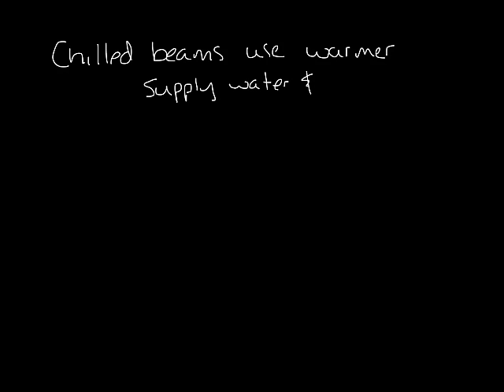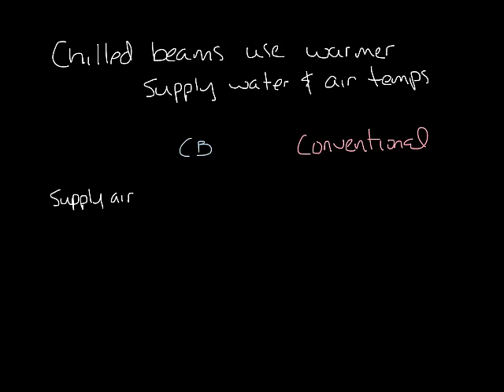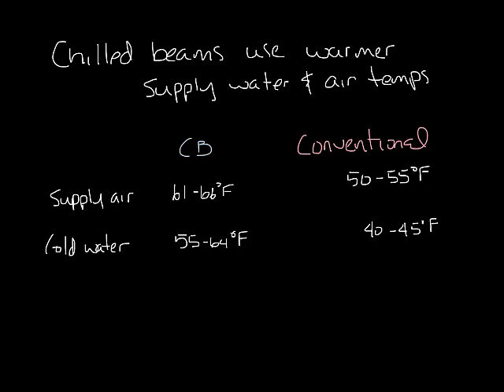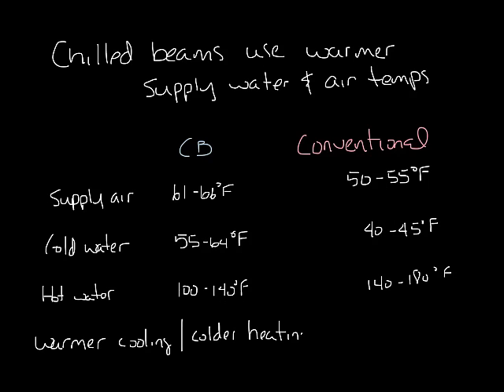Another benefit of chilled beam systems is that they use warmer supply water temperatures and warmer supply air temperatures than a conventional overhead air distribution system. For instance, the supply air temperature of a chilled beam system would be between 61 to 66 degrees Fahrenheit compared to 50 to 55 degrees in a conventional system. The cold water temperature would be 55 to 64 degrees for a chilled beam compared to 40 to 45 degrees in a conventional system, and the hot water temperatures are 100 to 140 degrees compared to 140 to 180 degrees for a conventional system. This warmer cooling temperature and colder heating temperatures will reduce the energy usage of the building.